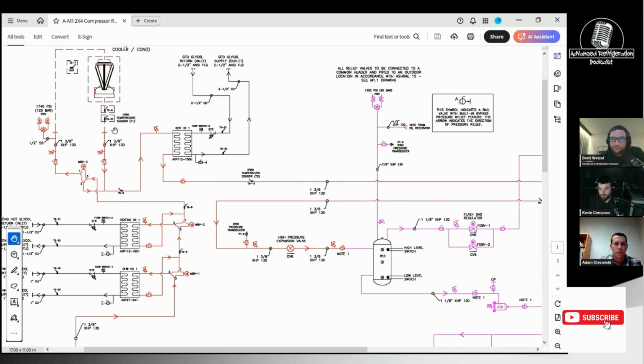Yeah. One thing we did on this rack to improve the heat recovery is a combination of things. One, you can increase the set point of this, which typical control algorithms do. But secondarily, if you're still not getting enough heat, then you increase the gas cooler outlet temperature. And that does 2 things. One, your discharge pressure still rises, but you're also now increasing the temperature going into your high pressure expansion valve. So that increases and changes the enthalpy, which then increases the flash gas. So you're adding artificial load to the compressor. By raising that, you're not only raising the discharge, but increasing flash gas.